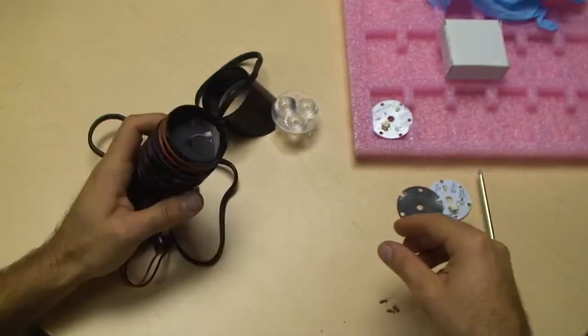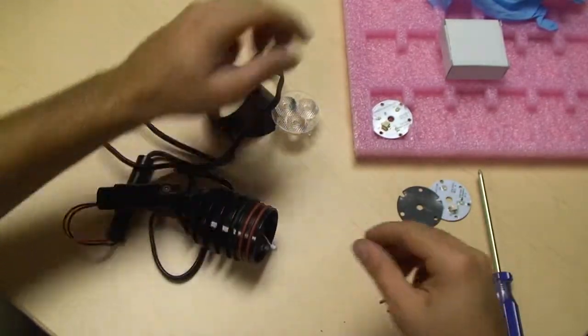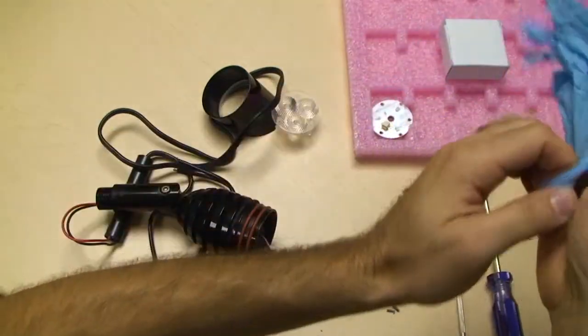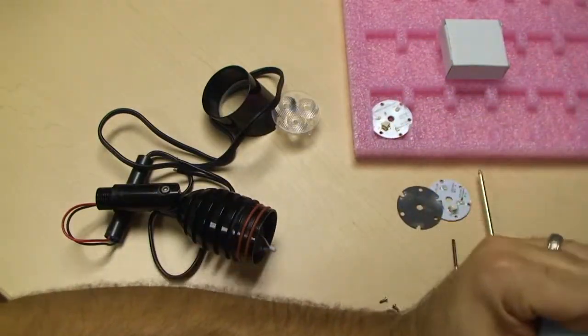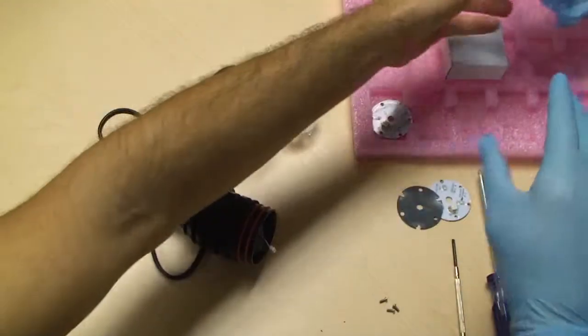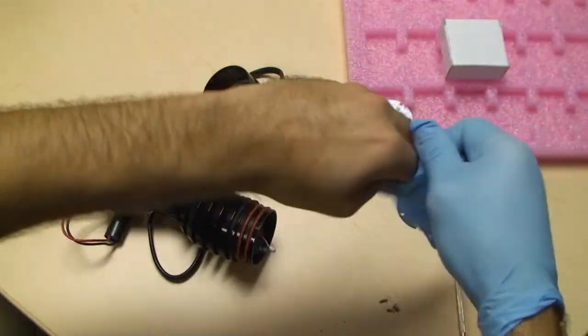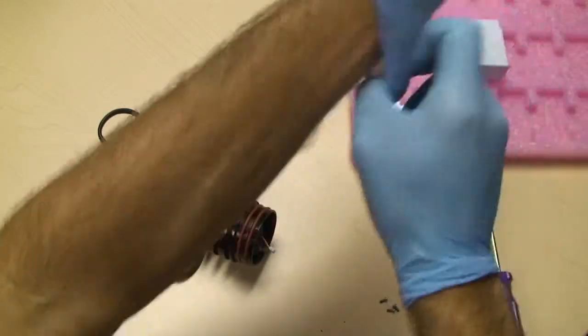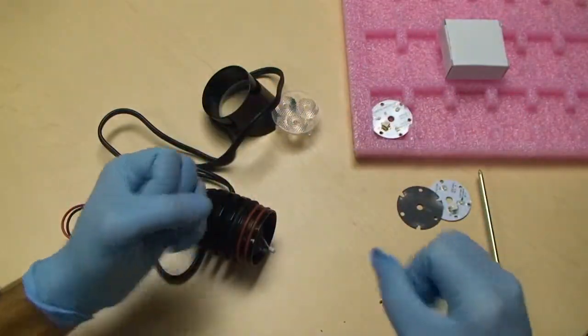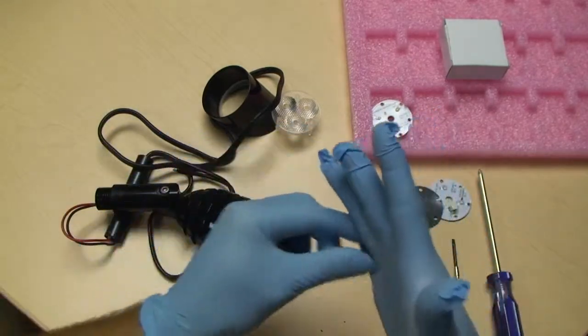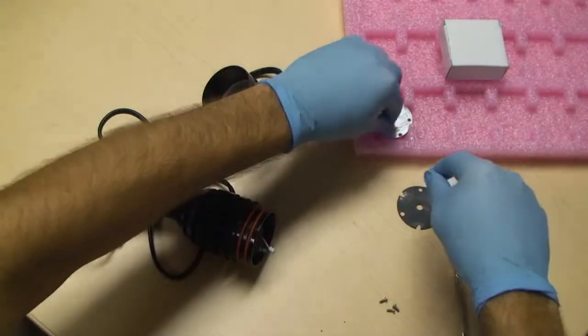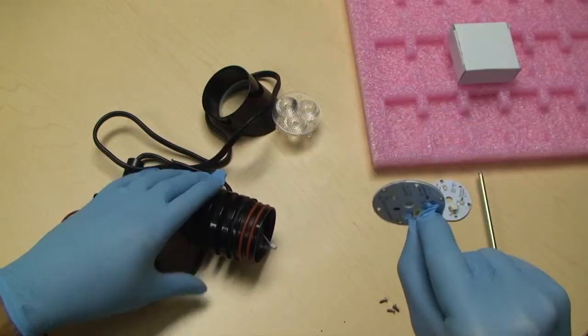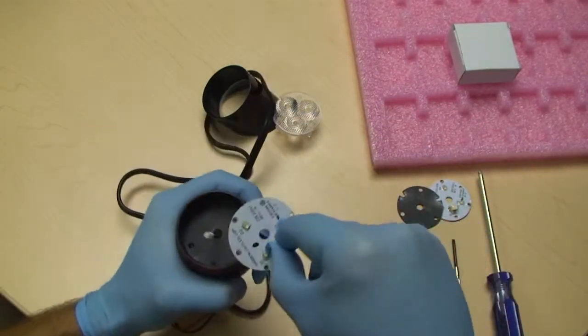Step 11. Put on your ESD safe gloves that were included in your LED board replacement kit. Carefully pick up the new LED board, making sure to hold it by the connector and lower it into place while aligning the holes correctly.